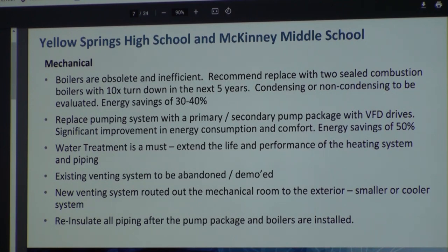We didn't do a load calculation, but if all three are running, you're really pulling a lot of air out of the building. So it's inefficient both from the perspective of gas consumption, and because you're pulling all this heated air that you just paid to heat back into the boiler room and up the flue.